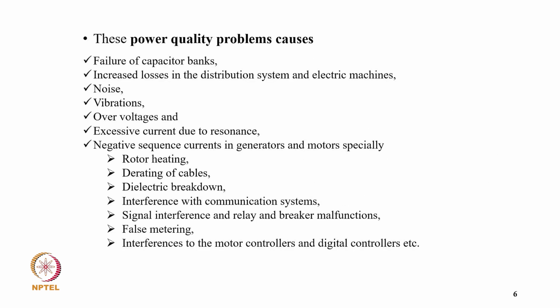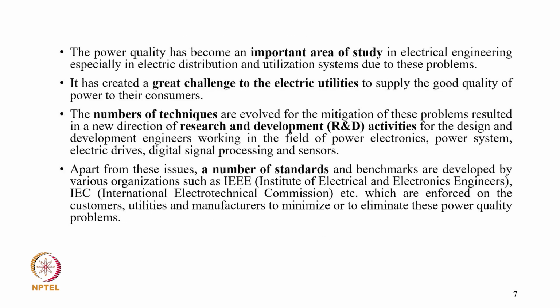So these power quality problems cause failure of capacitor banks, increased losses in the distribution system and electrical machines, noise, vibration, overvoltage, and excessive current due to resonance, and negative sequence current in generators and motors, which especially causes rotor heating, derating of cables, dielectric breakdown, interference with communication systems, signal interference, relay and breaker malfunction, false metering, and interference to motor controllers and digital controllers, etc.